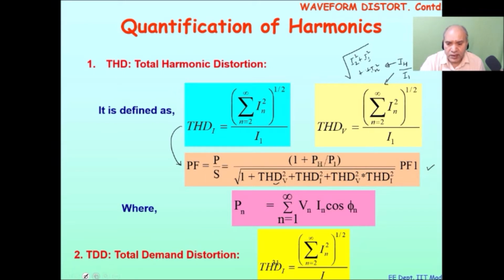And then another figure of merit is the total demand distortion. This is nothing but IH divided by IL. Okay. So the difference is this term. It is IL here, it is I1 here. Therefore, THD or TDD, this is not THD, this is TDD, please correct it. Okay. This is TDD. Therefore, TDD can never be more than 100% because it is the ratio IH by IL. Whereas THD could be greater than 100% depending upon the content of harmonics.